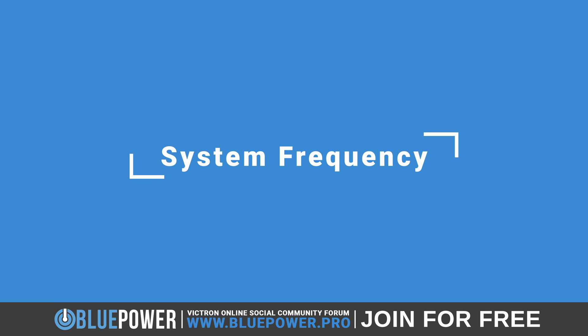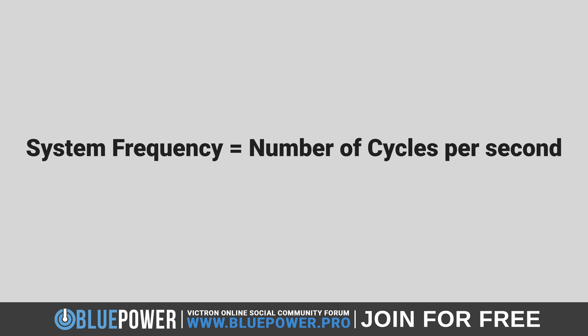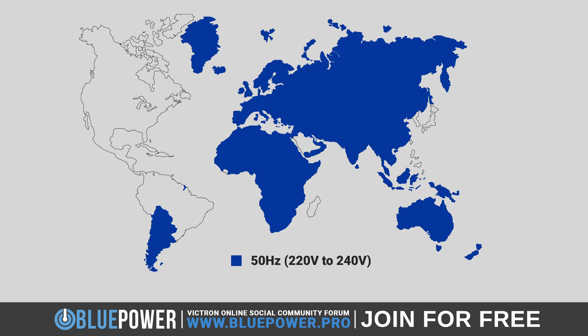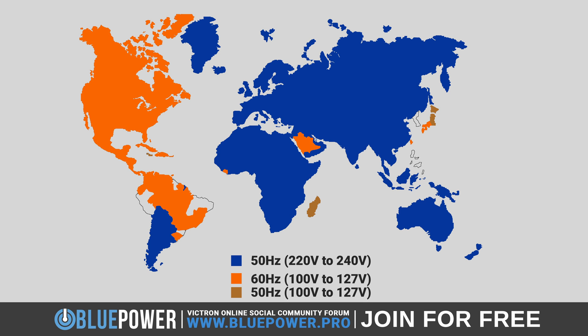Therefore, when setting up an inverter, the system frequency refers to the number of complete cycles the current goes through per second, measured in Hertz. The standard frequency of the electric current varies by country — 50 Hertz is the standard used in much of the world, including Europe, Asia, Africa, and Australia, while 60 Hertz is commonly used in North America, parts of South America, a few countries in Asia like the Philippines, as well as parts of Japan.